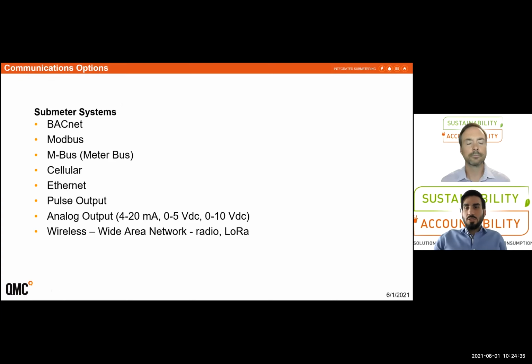Some of the communication options available from the metering systems range from analog outputs 0 to 5 volts, 0 to 10 volts, 4 to 20 milliamp or pulses, currently utilized typically for control purposes, to digital outputs from Modbus and BACnet and MBus or meter bus, which is standard for sub-metering or billing application these days. Communications along with encoded outputs from some of the billing grade meters, mainly water meters.